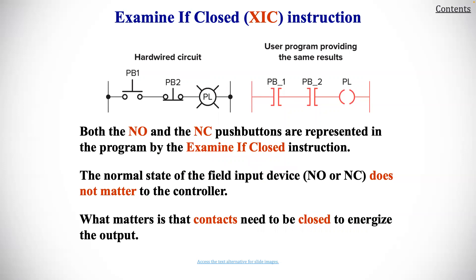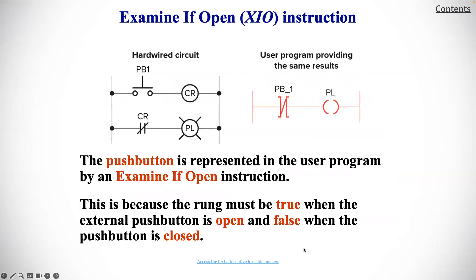Both the NO and the NC push buttons are represented in the program by the examine if closed instruction, XIC. The normal state of the field input device — NO or NC — does not matter to the controller. What matters is that the contacts need to be closed to energize the output.